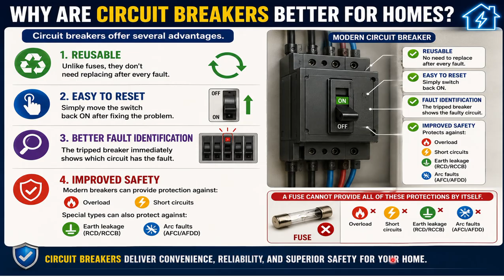Now we're going to talk about why circuit breakers are easy to use at home. Like I said, they are reusable. Unlike fuses, they don't need replacing after every fault. They are easy to reset: just turn it back on if the fault has been fixed. It is better for fault identification. If you go to your distribution board and there's a fault in the kitchen, the circuit breaker that controls the kitchen is going to go off, and you can identify that this fault is coming from this part of the circuit. It also has increased safety, because a circuit breaker doesn't just protect from overcurrent, it protects from short circuit and overload as well. That is one thing a circuit breaker has over a fuse. The fuse cannot provide all this protection. True, the fuse cannot protect against overload, short circuit, earth leakage, and arc faults, but modern circuit breakers can. One circuit breaker can protect against all of these faults.